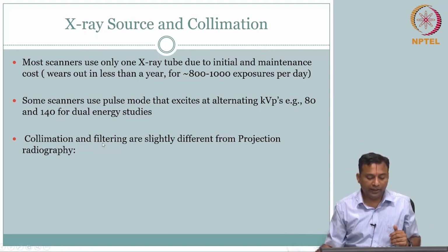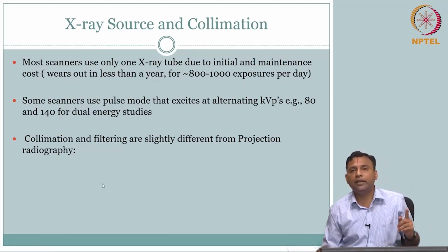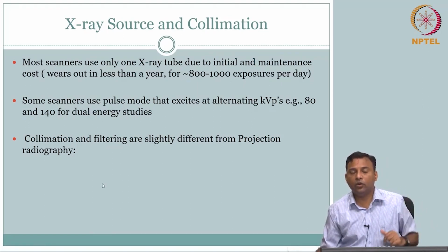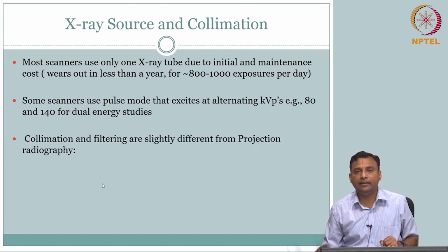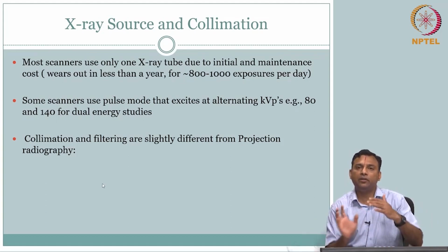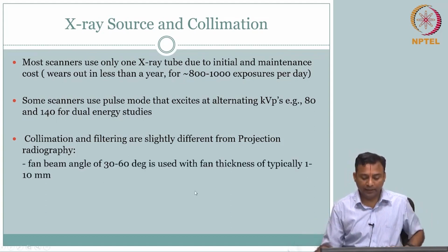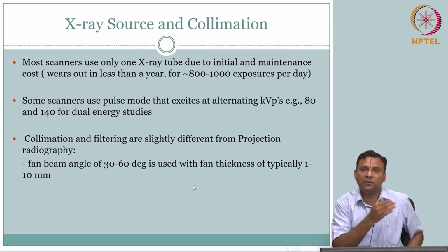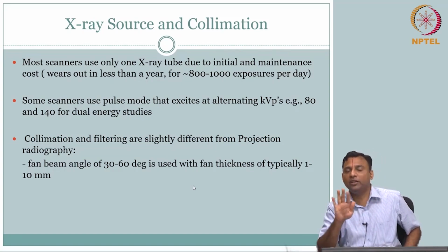When we talked about filtering, we talked about it in the context of removing the low energy, right. Here, deliberately, you make it hard. What do you mean by hard? Hardening the beam. Beam hardening, what does it mean? We covered this. You remove the low energy so that you are moving the spectrum to the right.